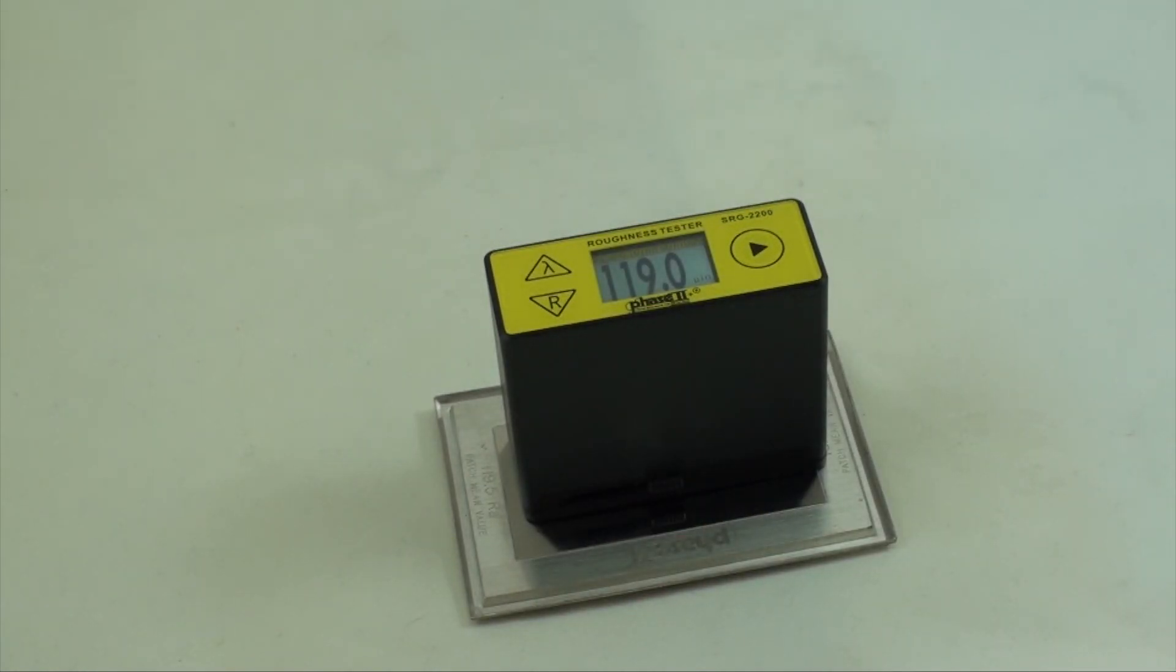The correct setting for your workpart can be found in a chart in the operation manual. The correct cutoff setting will be determined by the approximate surface roughness of the part. You can toggle between inch and metric measurement by holding the lambda button for two seconds.